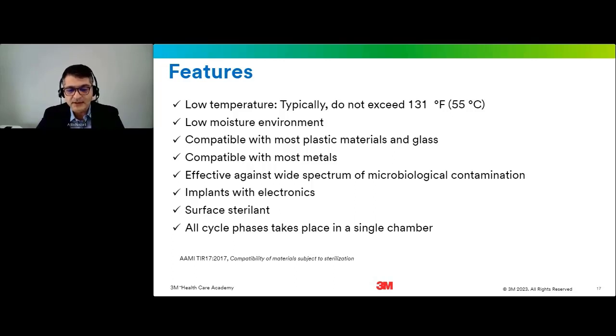All cycle phases take place in a single chamber. You don't need to aerate in another chamber. Another point I want to highlight is the compatibility with materials. It has good compatibility, but regarding medical devices to be used for each sterilizer, you also need to consult the instruction for use of the medical device to see which sterilization modality methods they have been validated to be used for.